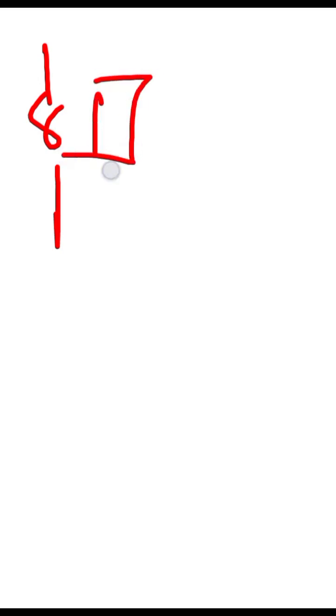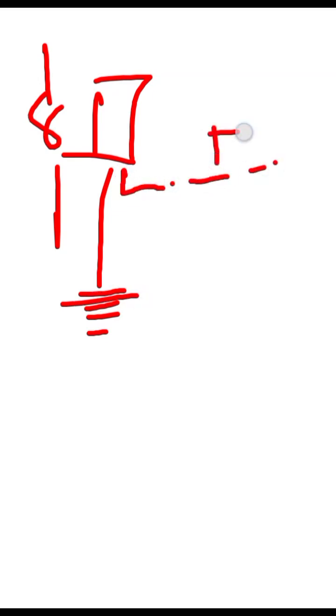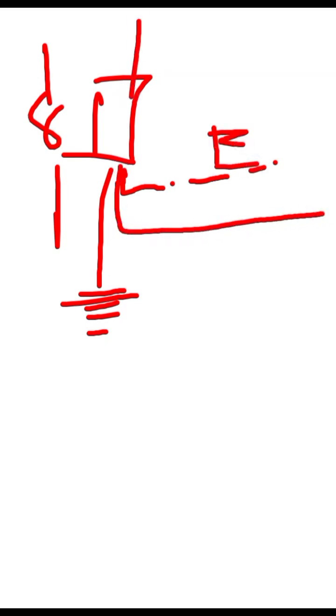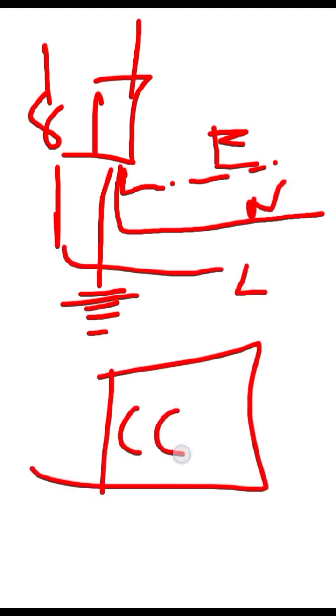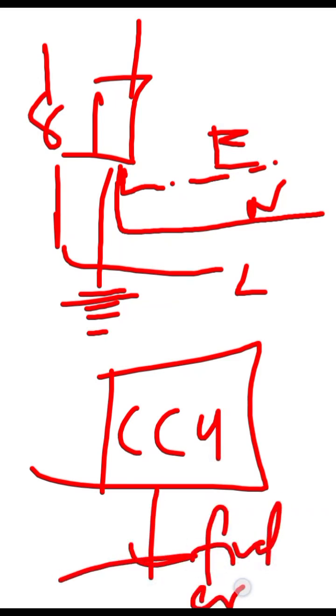So we're having a cutout, we're having the neutral link. Then from the neutral link, we take a cable that is grounded over there. We take another cable that we use as our earth going to your house, and the neutral wire which came from the drop going to your house. So you have now this live and neutral going to your CCU for the rest of the connection to your final circuits that you have in the house. And that is basically how we introduce an earthing system generally. But we're going to look at specific systems that have different ways of doing this.